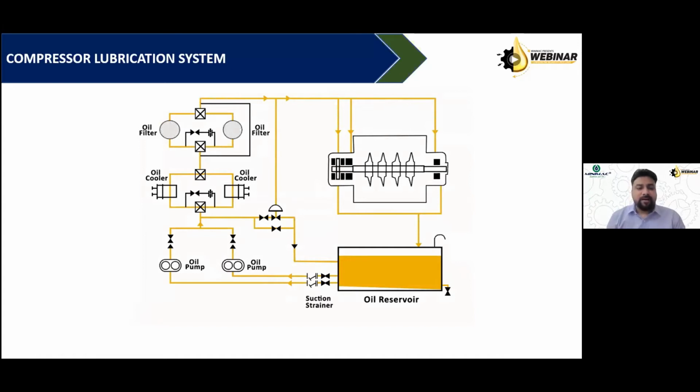Now here we must note that the OEMs of these compressors do give us certain duplex filter arrangements for doing the particulate separation from the circulating oil. But is that sufficient enough? Is that sufficient to remove the gaseous contamination? Does that solve the problem of foaming in compressor oil? Does that remove the water contamination which might have come along with the wet gas or the wet air? Does that remove the fine particles?